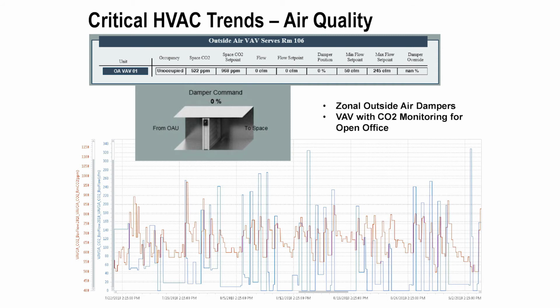So one thing that we looked at was, we have some unique systems here. Essentially, the whole building is demand control ventilation. So I wanted to make sure that my damper was really responding to my elevated CO2 levels, and you can see that here pretty well. So I feel decently confident that the demand control ventilation is working well over time.